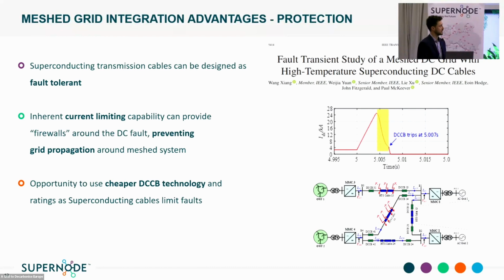Okay, and then the last key advantage. What I'm presenting here is the outcome of some research we've done with Professor Lee's research group on the integration and operation of meshed DC grids using our superconducting cable technology. Firstly, superconducting cables can be designed to be fault tolerant, so they can run in an overload condition, as you can with copper cables. But there's an inherent current limiting capability that a superconducting cable can also provide, and that's what we're leveraging in this study. You can see that when there's a fault...